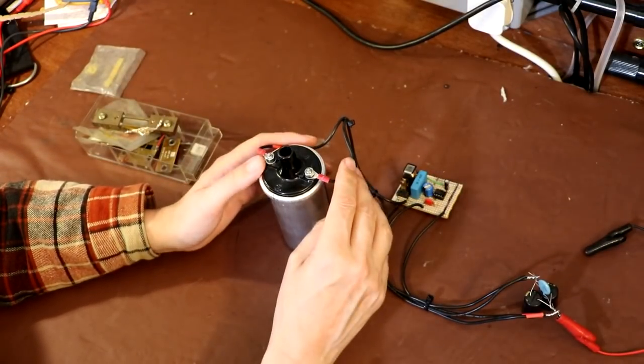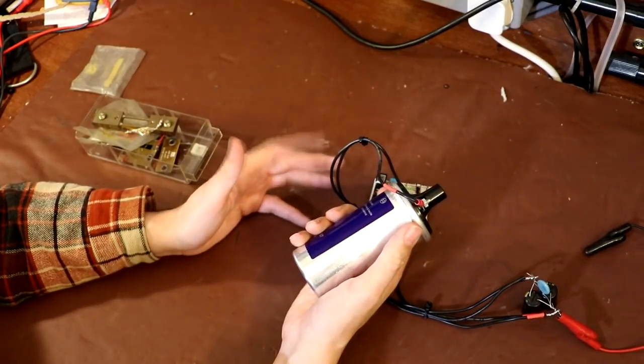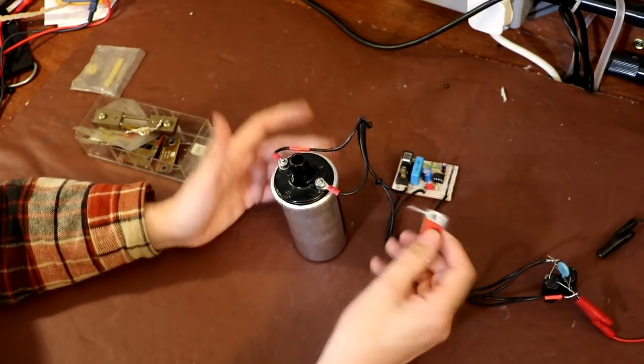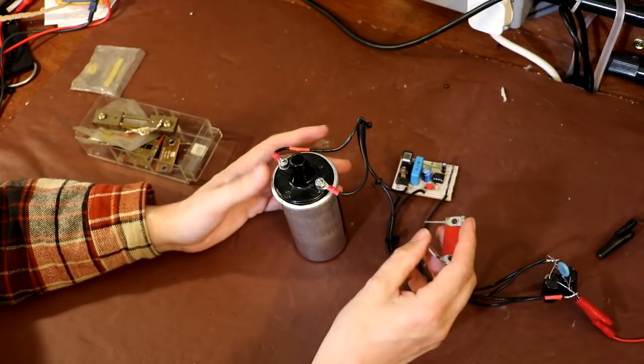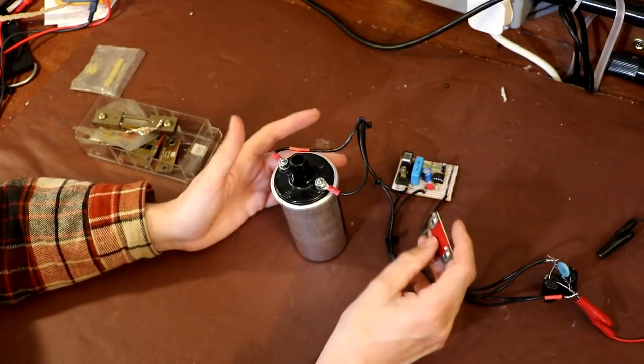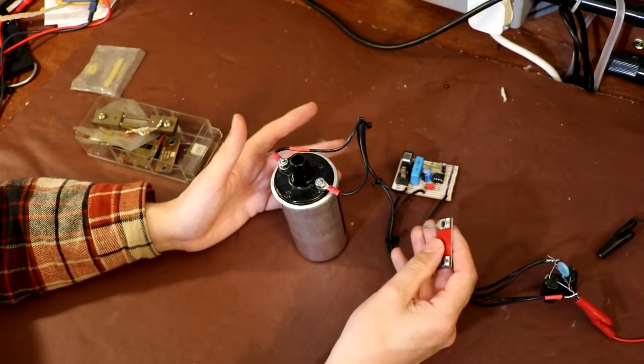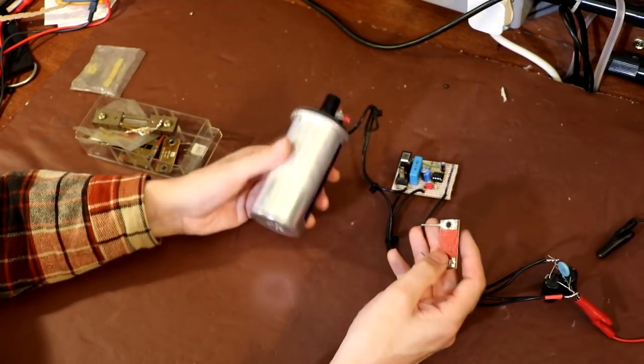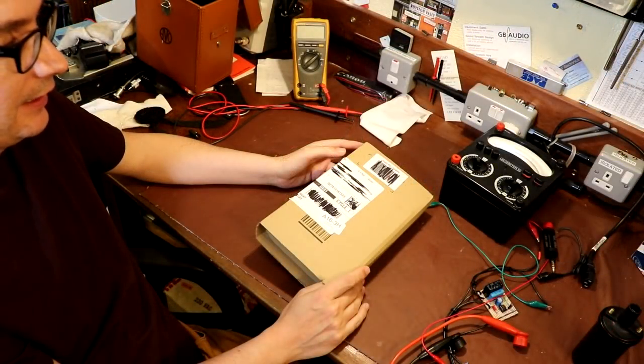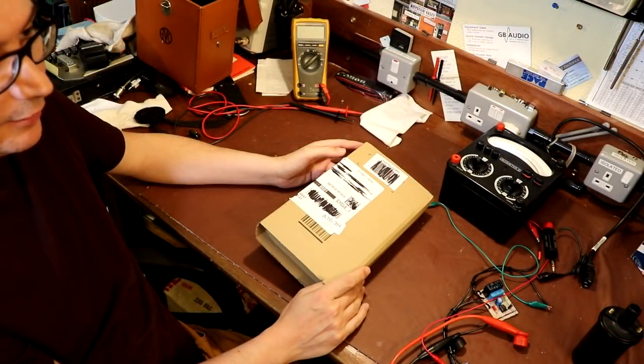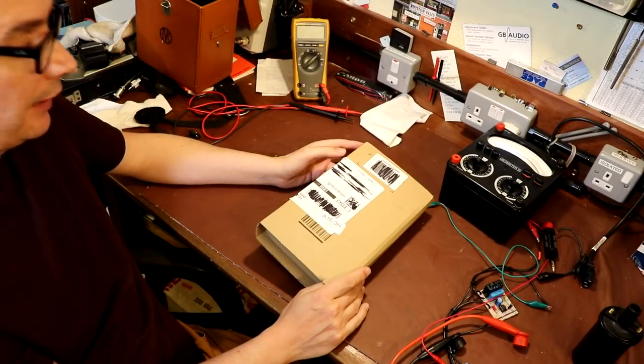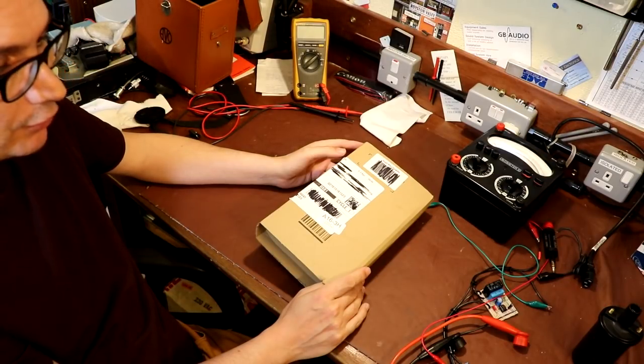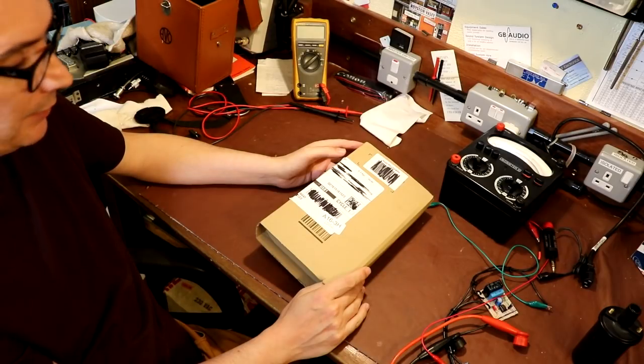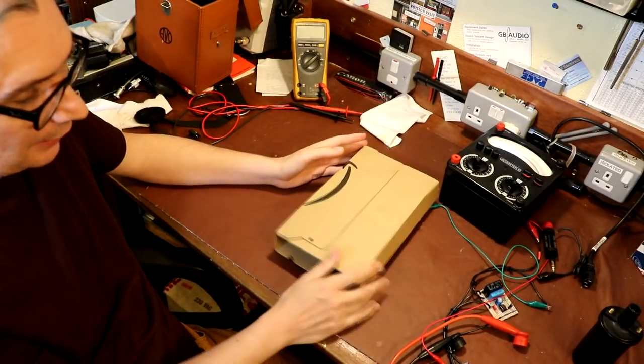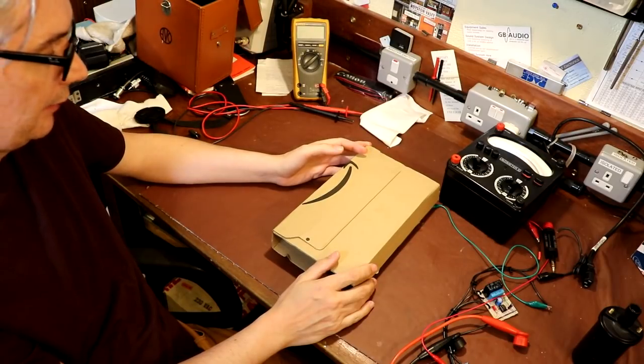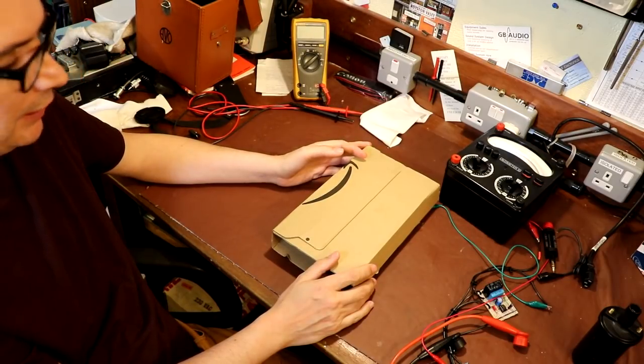I'm always a little cautious taking measurements on inductive loads. I prefer not to connect test equipment directly to them, and the better way is to use something called a current clamp. Back in the day, I bought a Tektronix current clamp probe for several hundreds of pounds, a very expensive bit of kit, and the specification wasn't amazingly high. I do have a Tektronix probe, but it's buried in the hoard somewhere, not sure where.